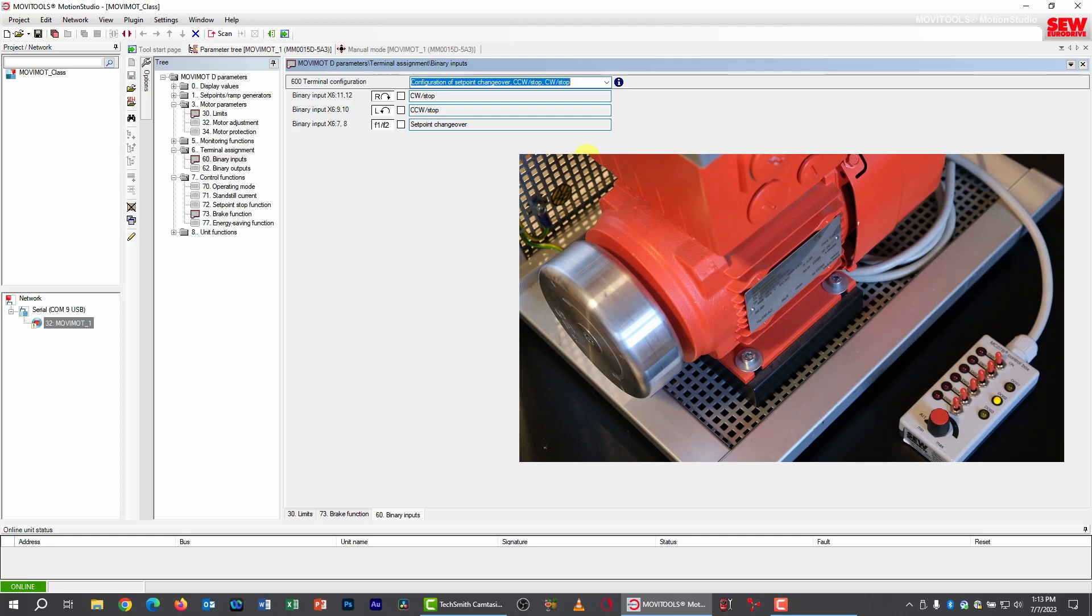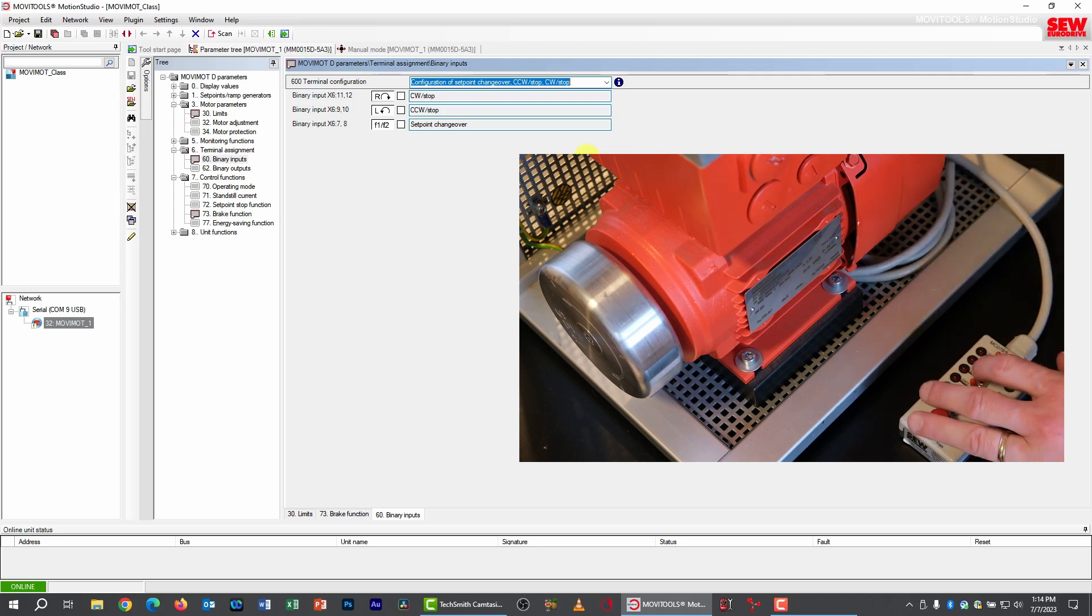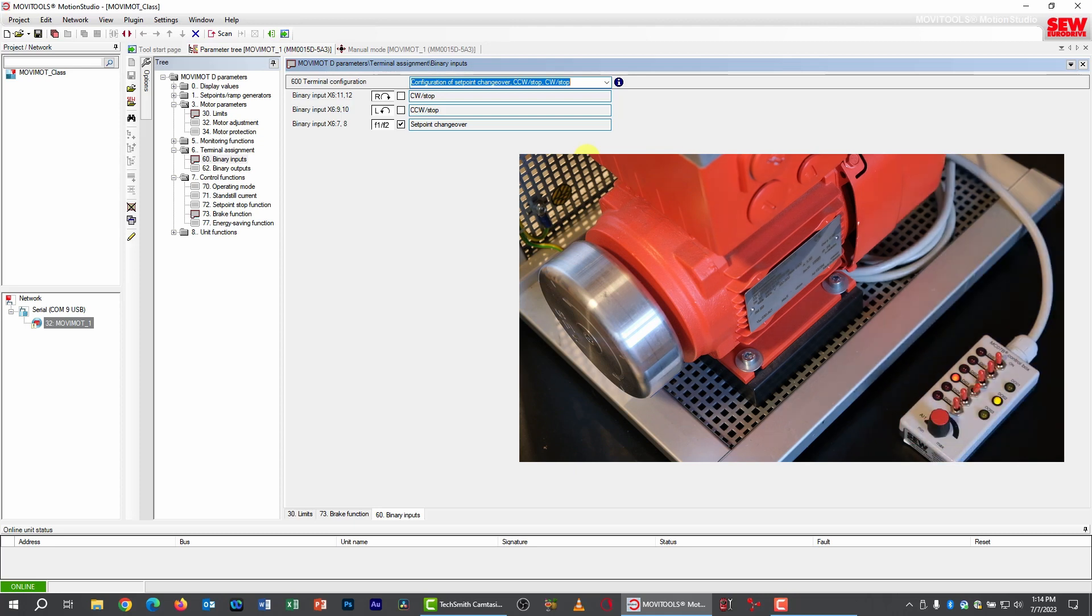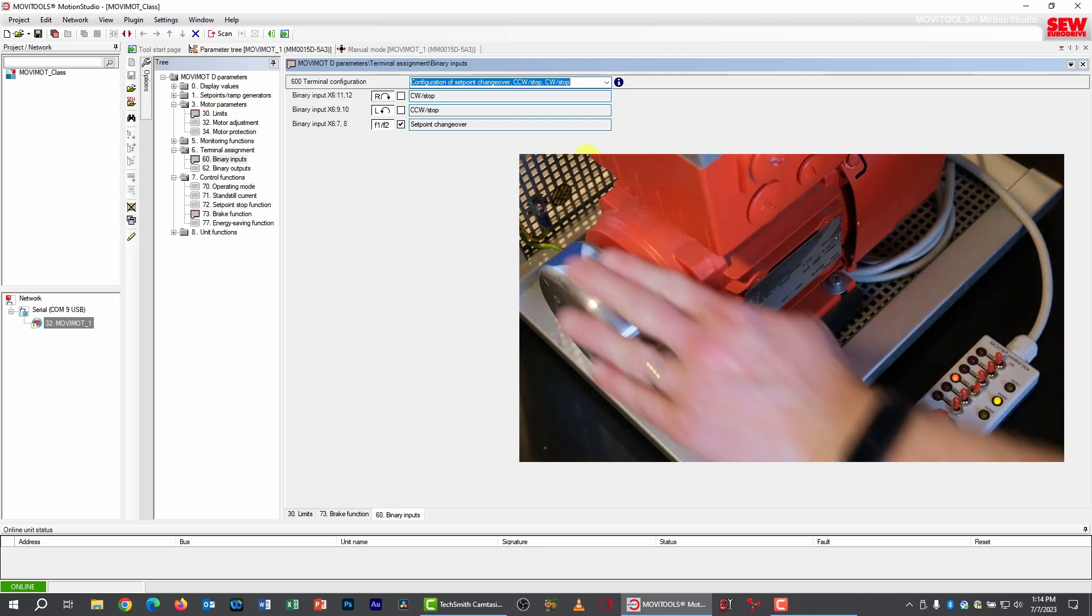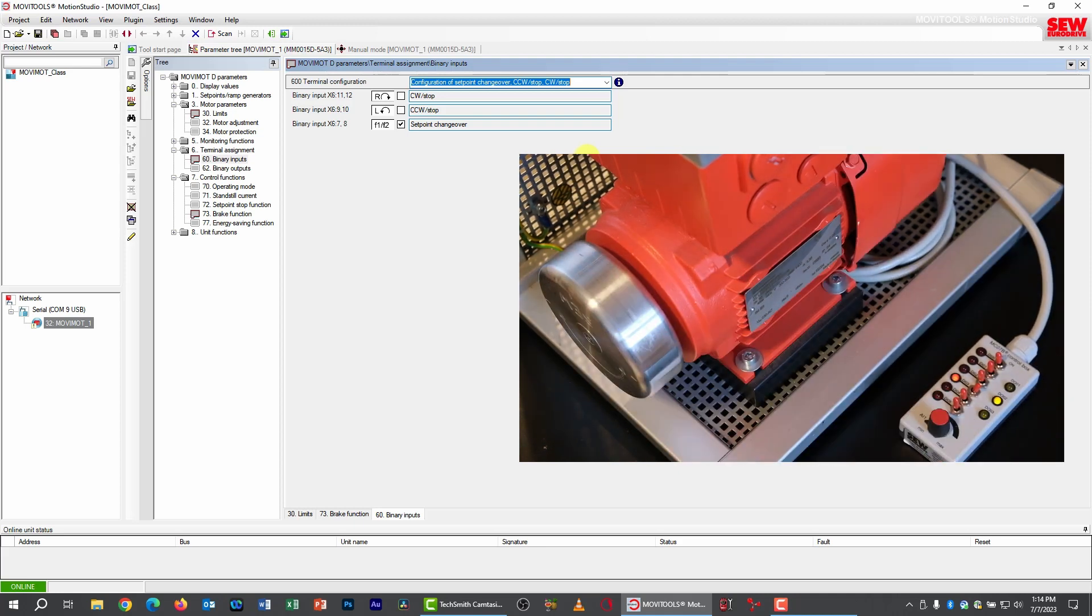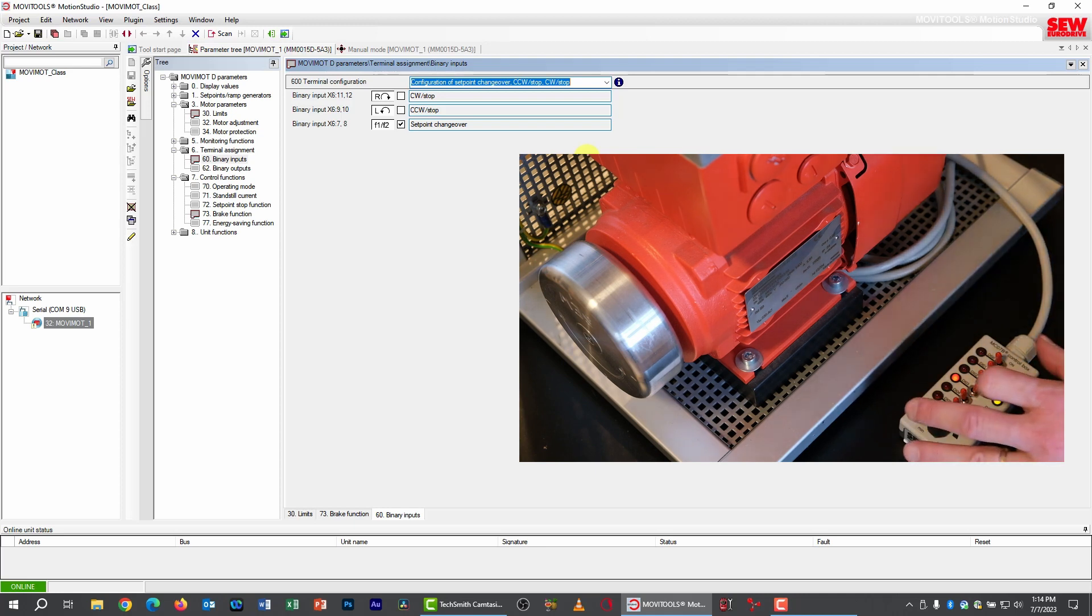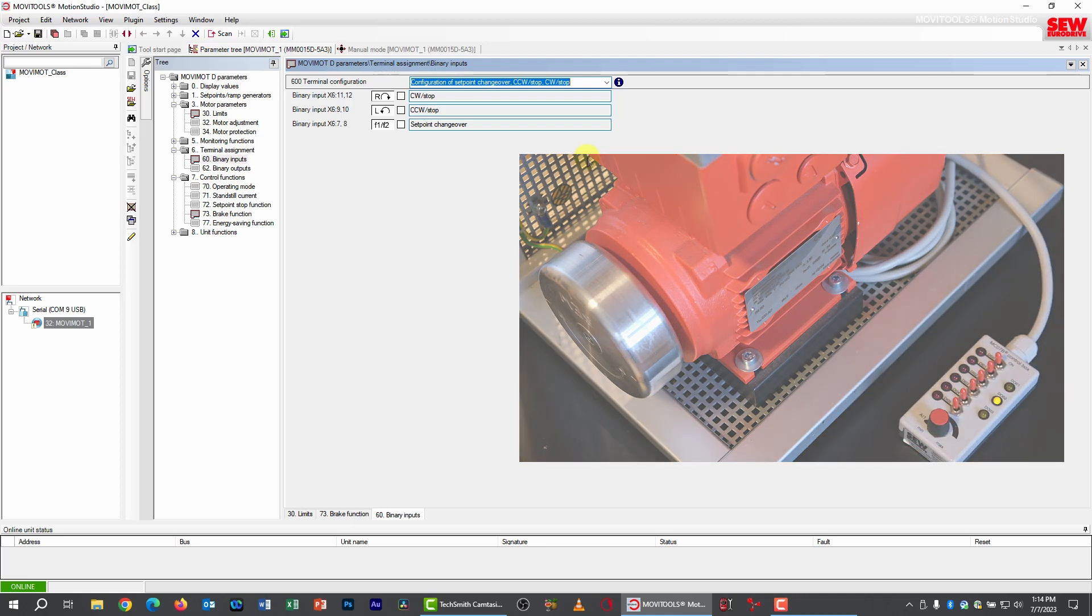Now I've stopped my drive. However, the F1, F2 signal now has an alternative function when the drive isn't turning, and that's a brake release signal. Let me turn the F1, F2 switch back on, but not turn the motor on. I just heard a clunk. That means the brake released, and now I can actually turn the motor freely. So the F1, F2 switch performs this extra function when we enable that feature either through the parameter or the DIP switch. Let's engage the brake again. So there we go.